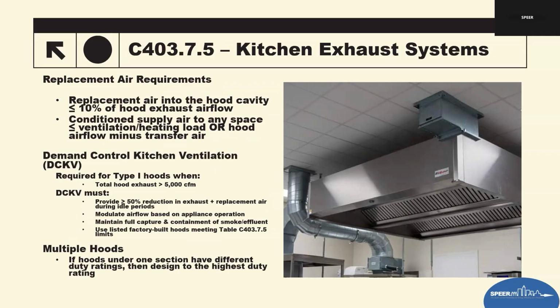There was a fan efficacy for those, but now they're starting to address even different sizes of the equipment. So one of the largest energy uses in restaurants, food services, and institutional kitchens: the 2024 code now has a stricter control for makeup air, airflow reduction, and when DCKV is required. So that's the demand control kitchen ventilation is required.